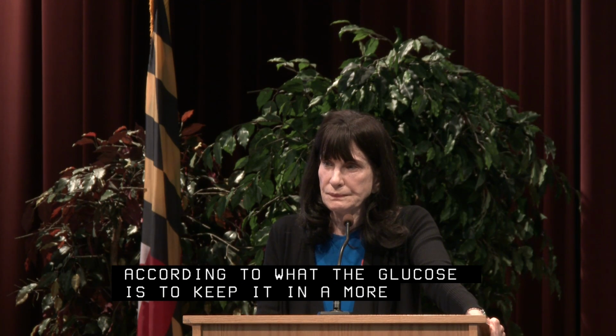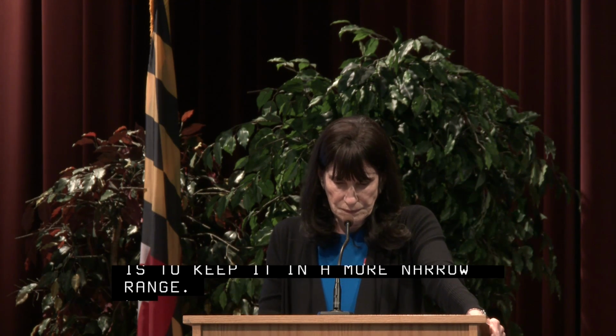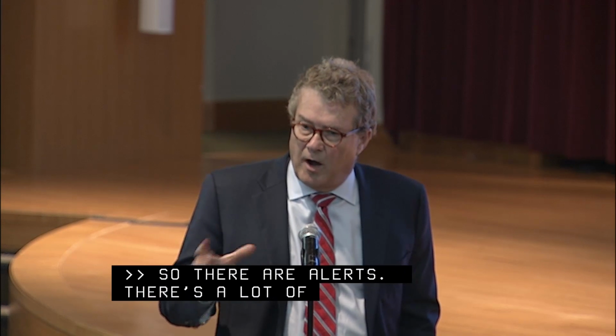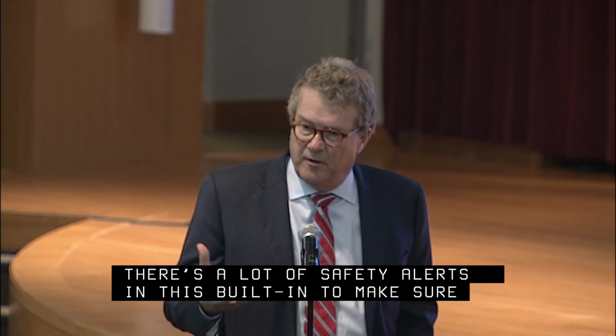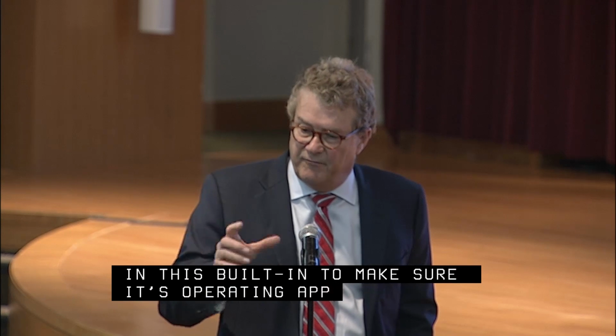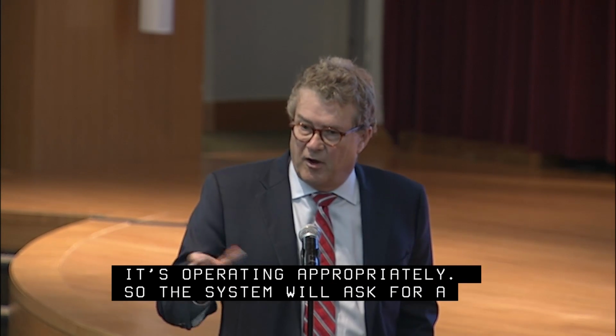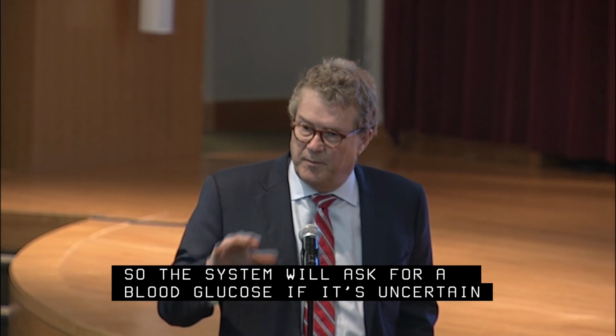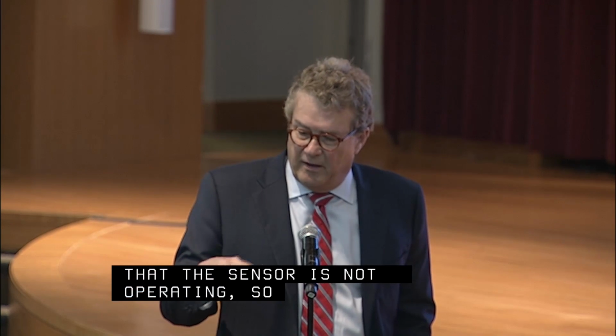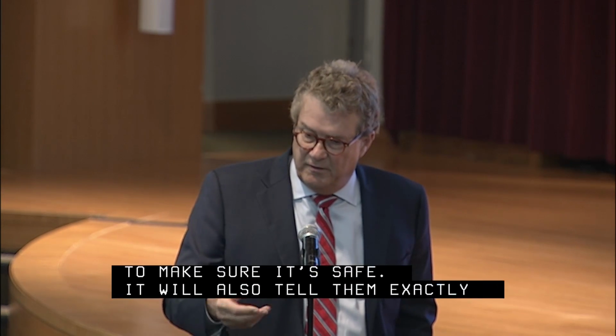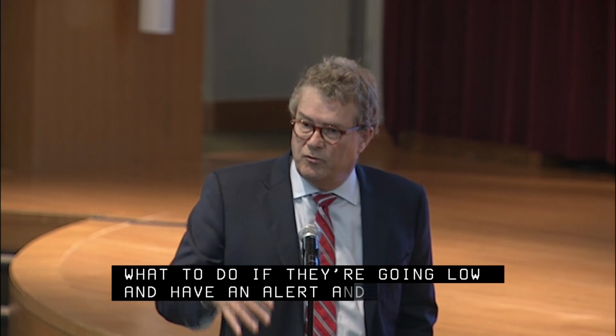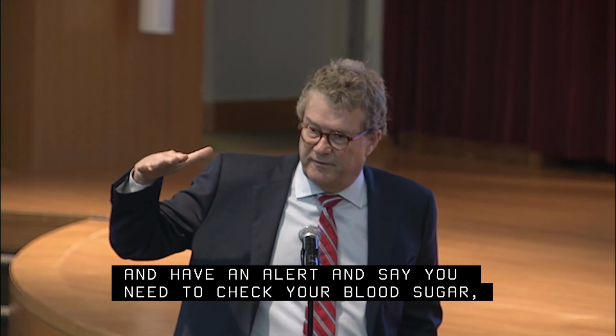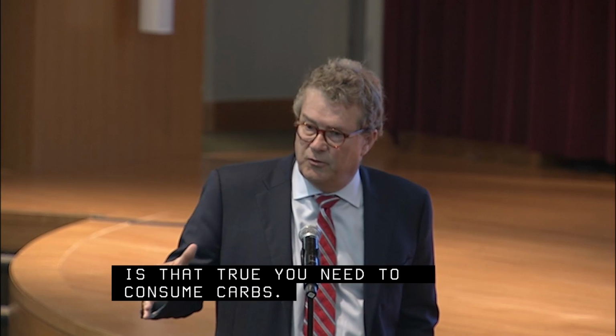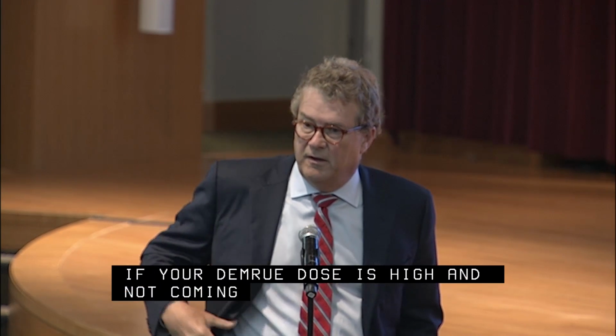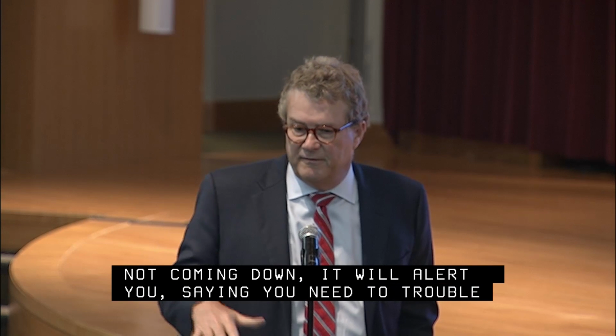Yeah, so there are alerts. There's a lot of safety alerts built into this to make sure it's operating appropriately. So the system will ask for a blood glucose if it's uncertain that the sensor is operating, so they put that in to make sure it's safe. It will also tell them exactly what to do if they're going low. It'll have an alert and say, you need to check your blood sugar. Is that true? You need to consume carbs. If your glucose is high and not coming down, it will alert you saying you need to troubleshoot your site. Is your sensor working? So it has all these safeties in it.